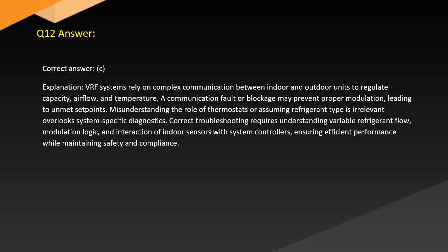Answer. Correct answer. C. Explanation. VRF systems rely on complex communication between indoor and outdoor units to regulate capacity, airflow, and temperature. A communication fault or blockage may prevent proper modulation, leading to unmet set points. Misunderstanding the role of thermostats or assuming refrigerant type is irrelevant overlooks system-specific diagnostics. Correct troubleshooting requires understanding variable refrigerant flow, modulation logic and the interaction of indoor sensors with system controllers, ensuring efficient performance while maintaining safety and compliance.